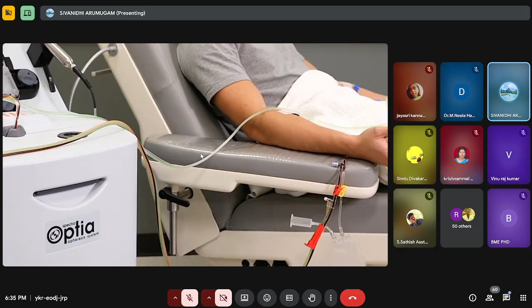I've mentioned pumps and valves, right? The main components. We call these pumps, rotor. Each pump has its own function. This we call the AC pump. This is responsible to deliver AC from the bag to the centrifuge. And this one is the inlet. If this rotates, it means it is taking blood from the donor and giving it to the centrifuge. This one is the plasma collection pump, and this one is the platelet collection pump. And here we have one big pump, that is for return. Once we're done with the collection of the required component, that is responsible to deliver the remaining components to the donor. Okay, so this is about pumps.